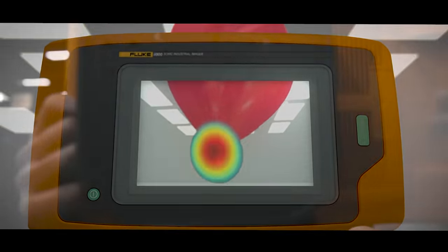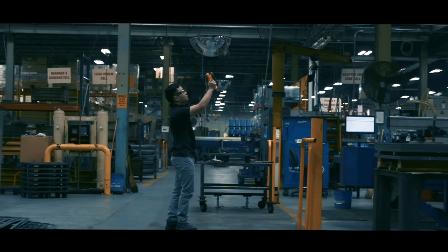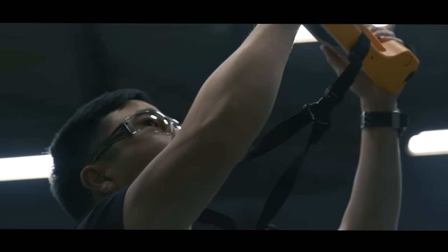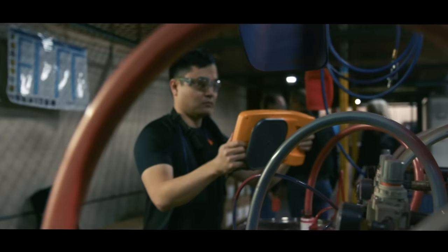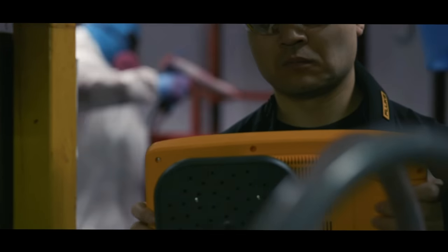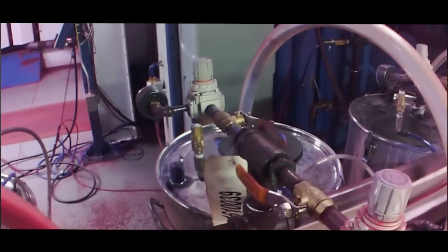If you rely on compressed air, you can now forget about the old messy way of finding leaks. The new Fluke Sonic Industrial Imager uses patented SoundSight technology, enhanced scans to clearly see leaks you can't even hear.